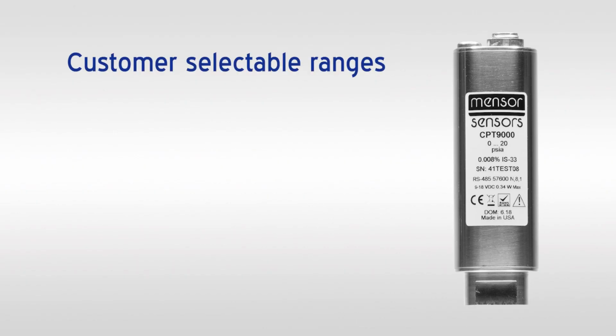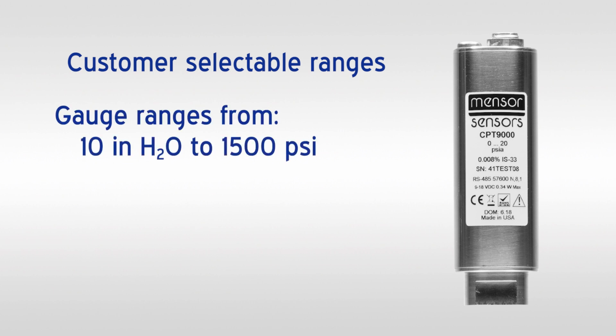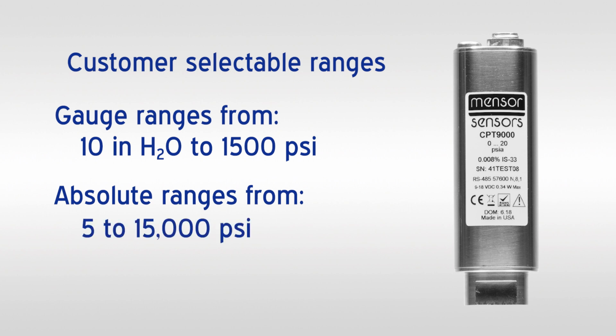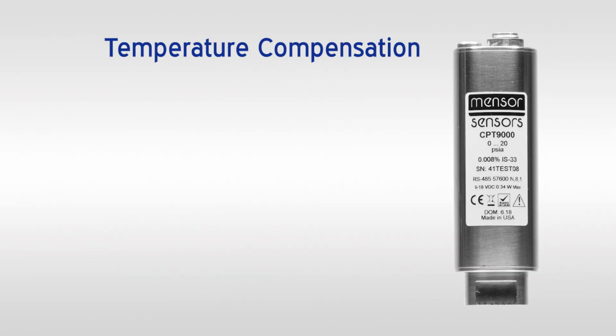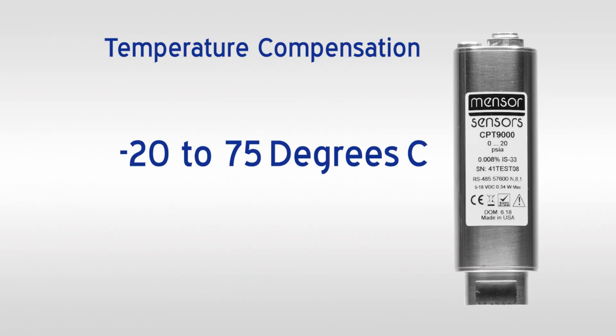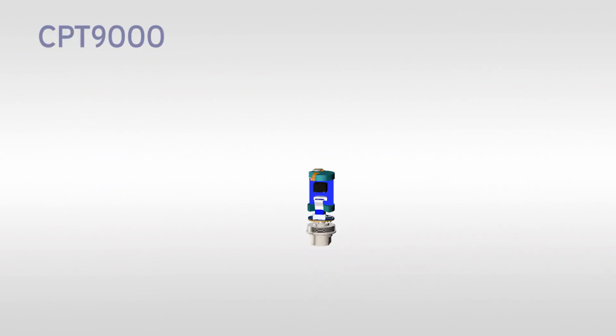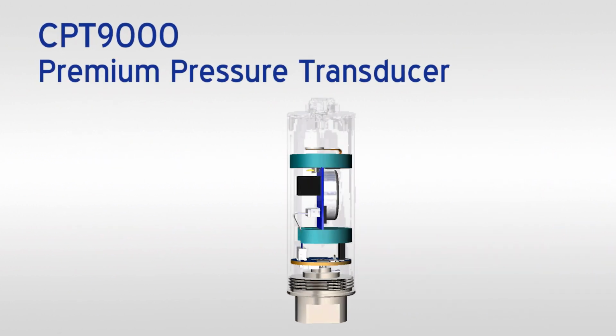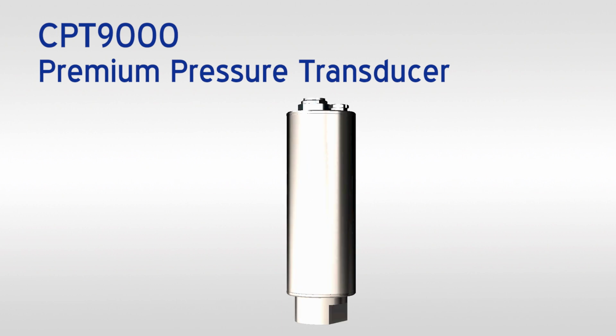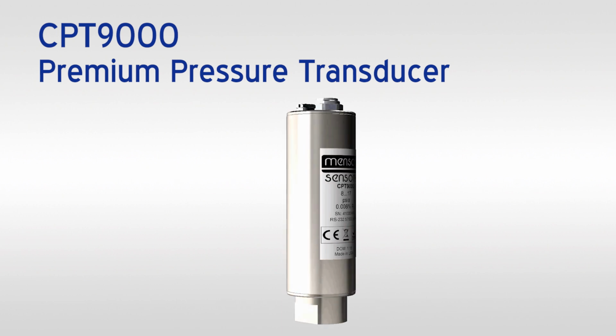The CPT9000 is configured with a range according to specific customer requirements, extending from 10 inches of water up to 15,000 PSI. No matter what pressure range is chosen, the temperature compensation is from negative 20 to 75 degrees Celsius, allowing for the transducer to be used in extreme conditions. All these features make the CPT9000 the premium choice for precision pressure measurement.